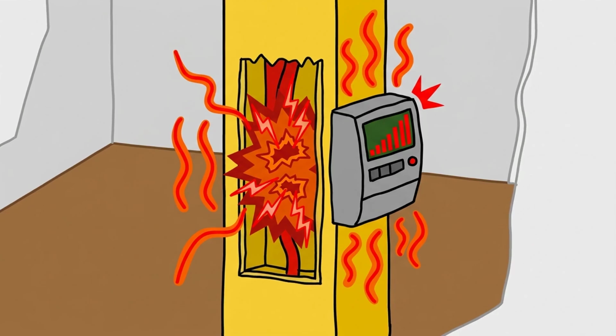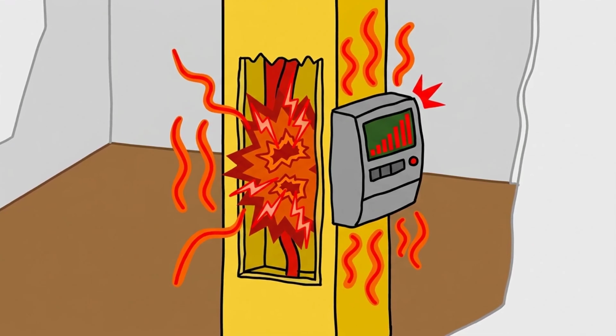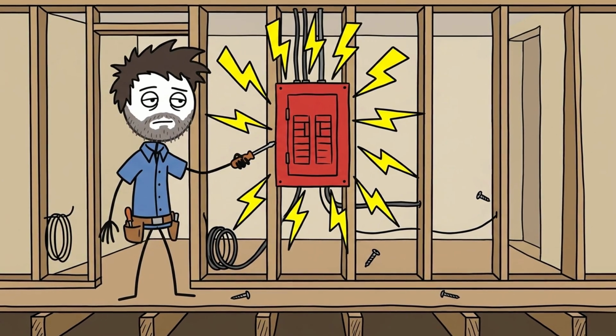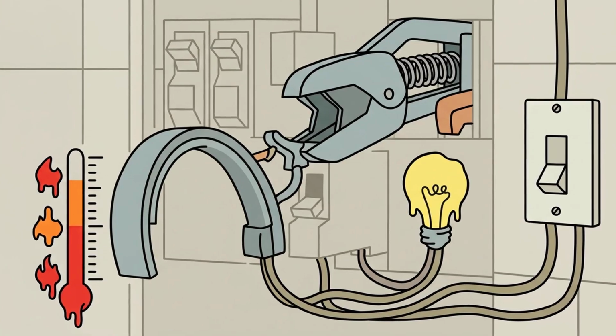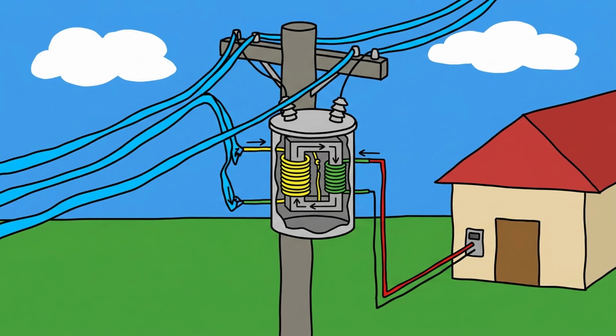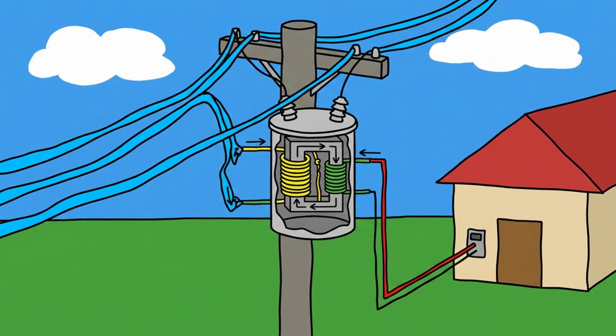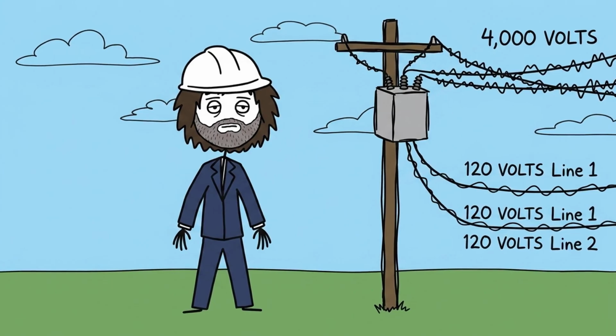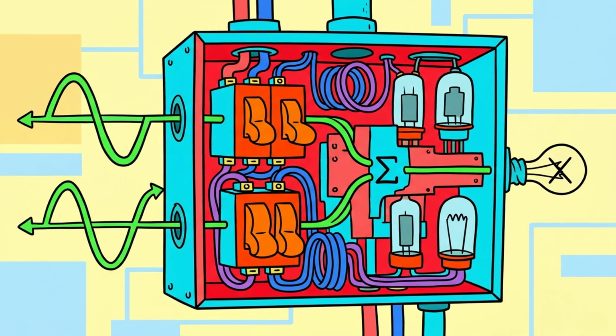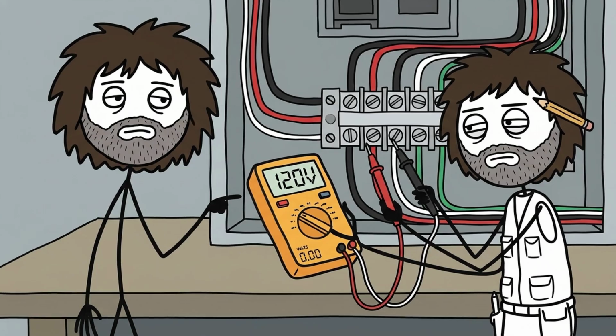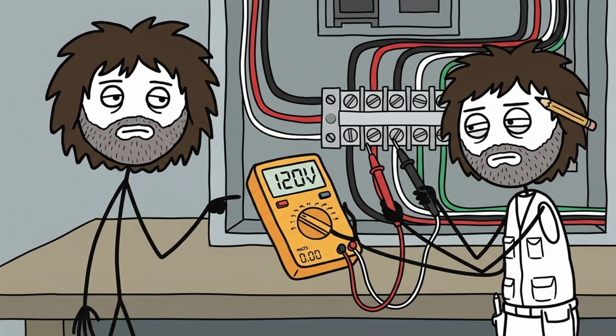The GFCI sensor detects this microscopic imbalance, as small as 4 to 6 milliamps, and trips the internal relay in 25 milliseconds, shutting down power long before electrical shock can cause cardiac arrest. While GFCIs stop electrocution, arc fault circuit interrupters, or AFCIs, stop structural wood fires caused by damaged wiring.